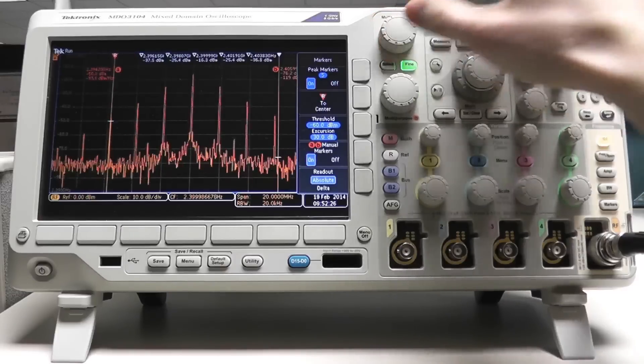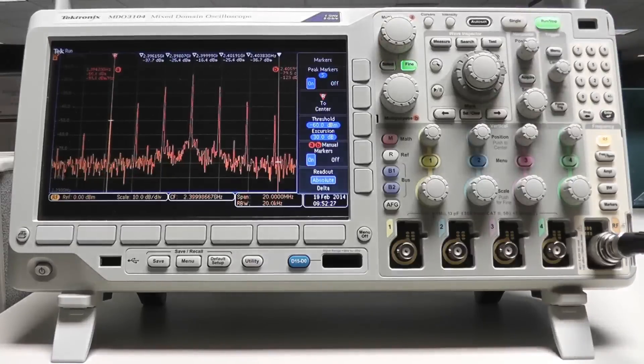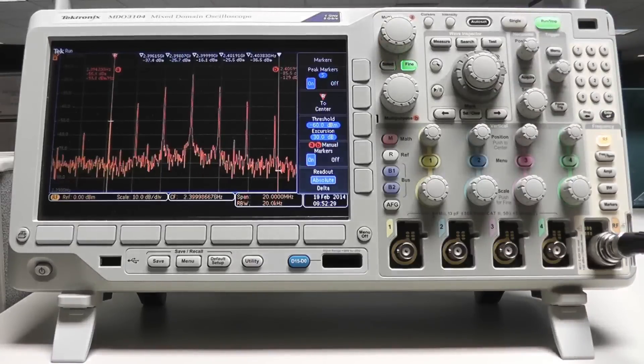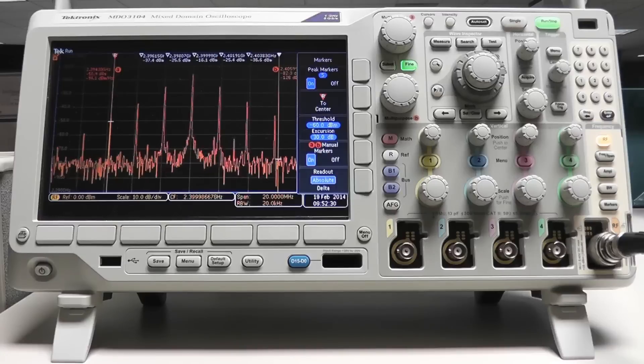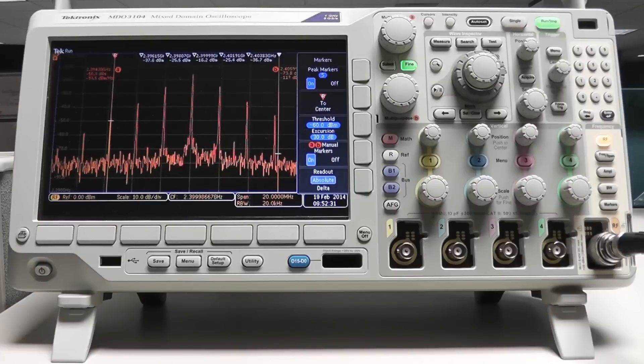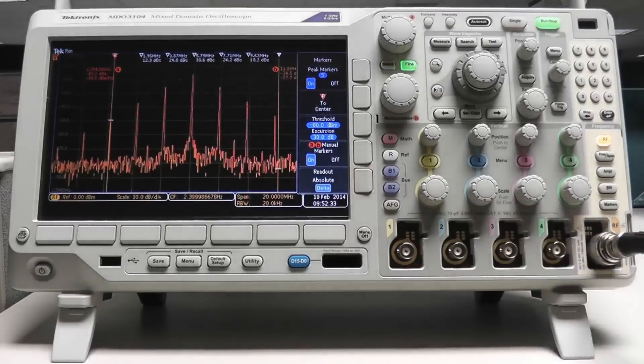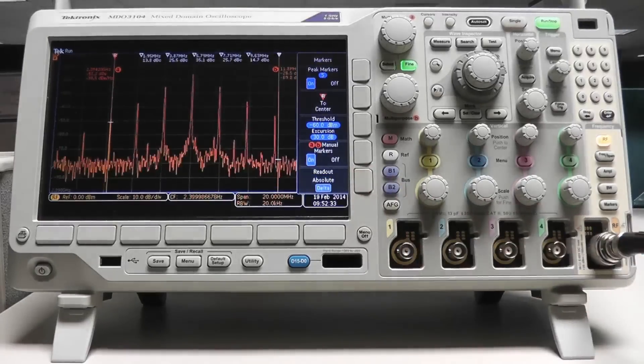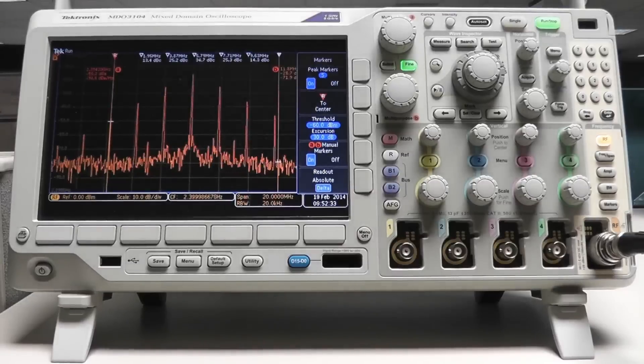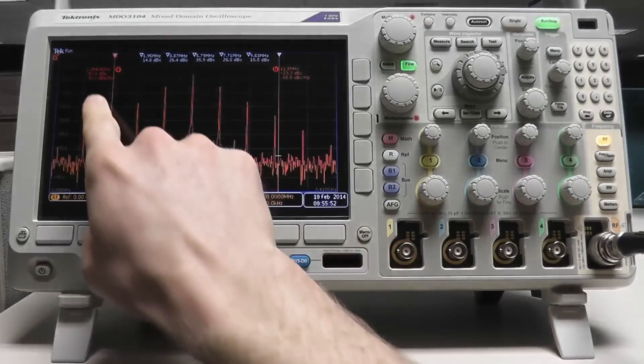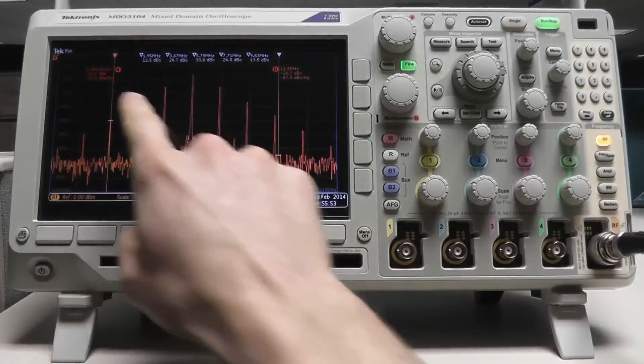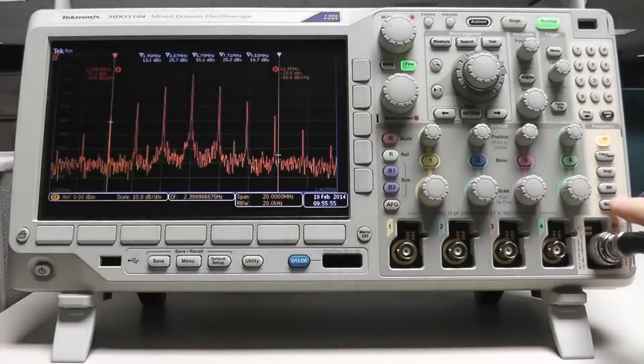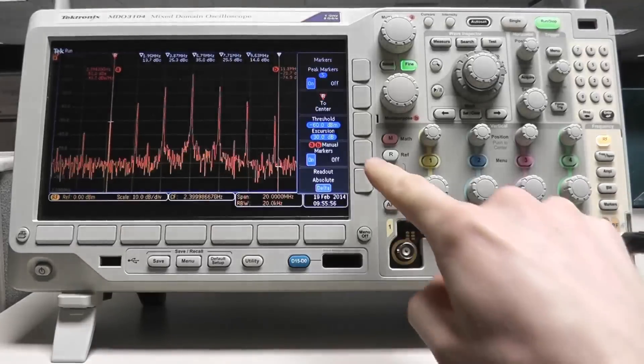The marker readout can be changed from absolute to delta. When delta is activated, the frequency and amplitude information on each marker is referenced to the reference marker, and if manual markers are active, noise density is applied to marker A, and phase noise information is applied to marker B.